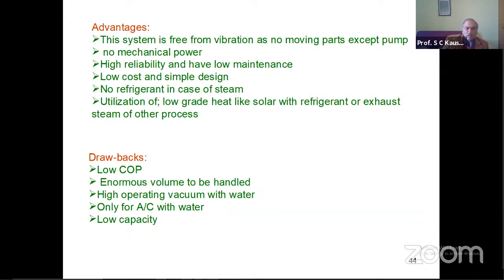But the major drawbacks are low COP and the enormous volume of vapor phase that has to be handled, high operating vacuum with water, and only air conditioning can be achieved, with low cooling capacity. So we have to go for the vapor absorption refrigeration system. Now let me tell you why vapor absorption refrigeration system.